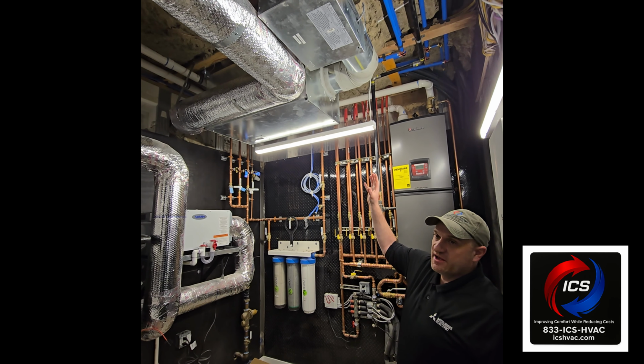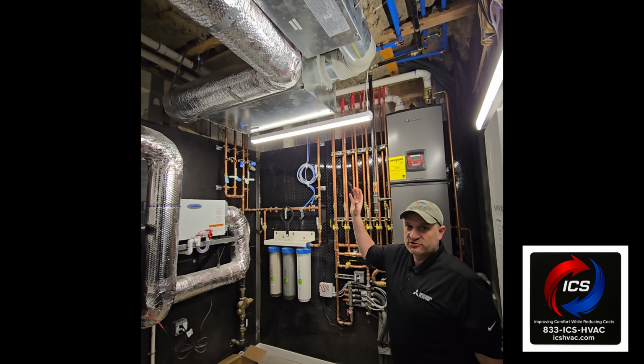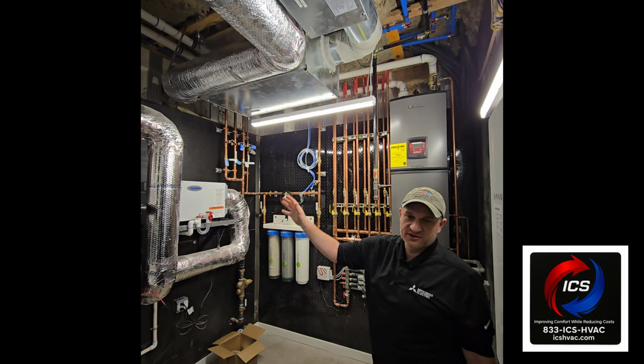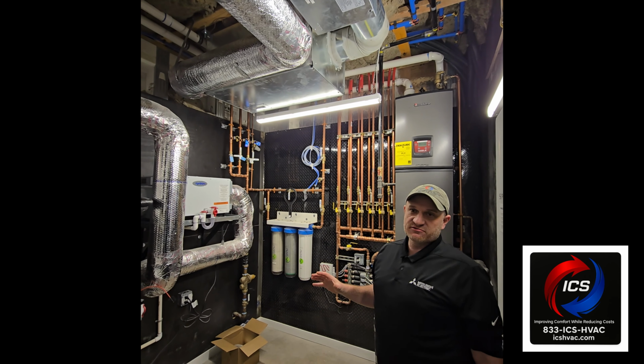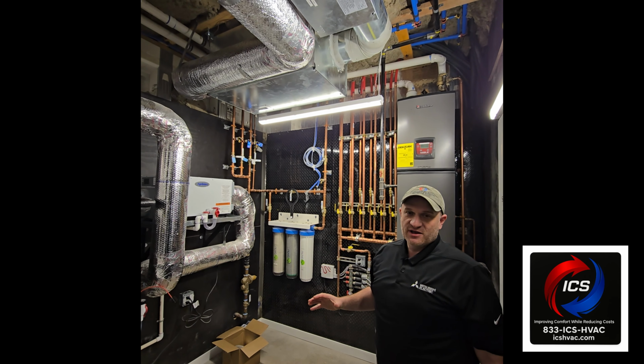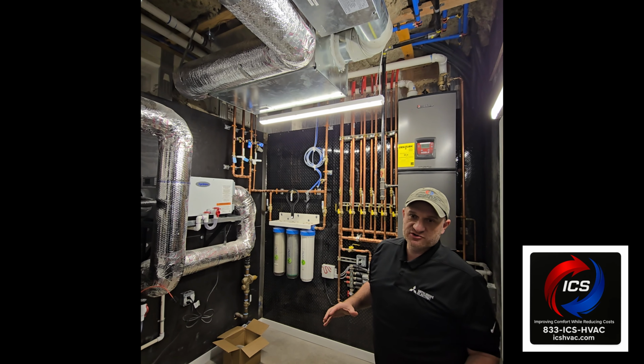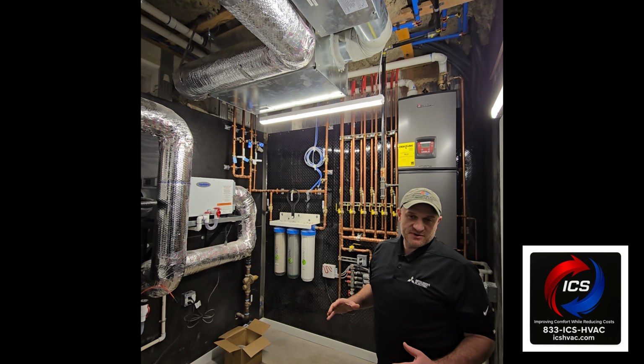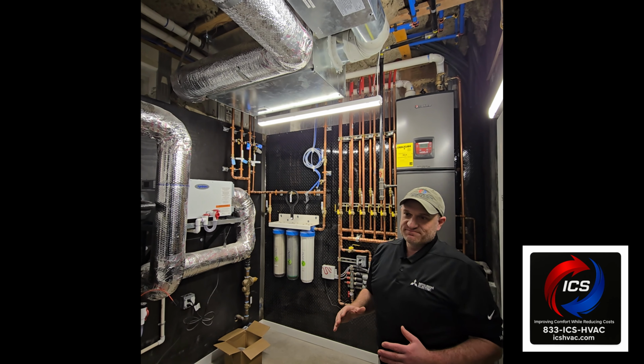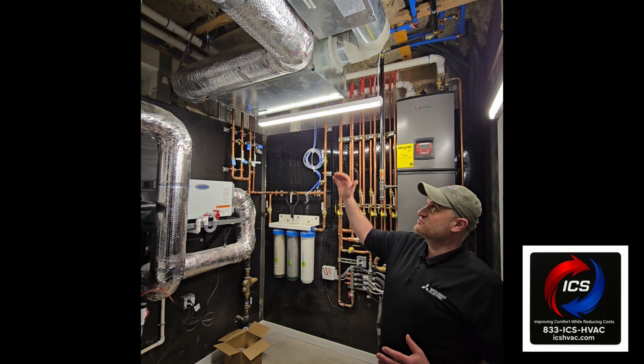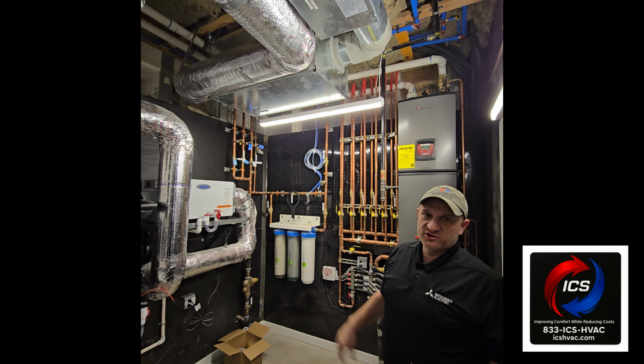This system has control wiring out to the exterior mounted exhaust fan. We have a current sensing relay out there that picks up how much amperage the exhaust fan is drawing. So depending on what fan speed the fan is on, it's either 3 amps or less, and this will ramp up and ramp down according to that input.